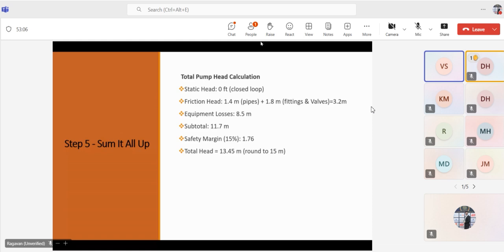Okay, then the final one. Once you calculate all the losses, the pipe losses, fitting losses, valve losses, equipment losses, then you have to add everything together. So combine all the pressure losses, including the pipe friction losses, fitting losses, valve losses, equipment pressure losses, and then add the safety margin. That is a very important one to obtain the final chilled water pump value.